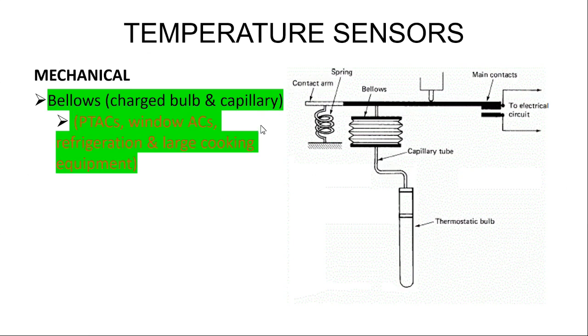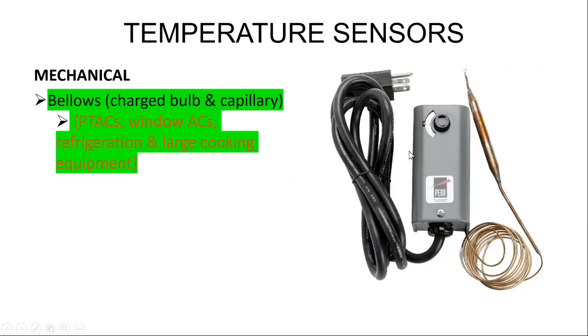You have the opposing spring tension, which opposes the action of the bellows. Here you have your adjustment stem. Where it is set determines how much the bellows must expand or contract in order to close these electrical contacts. Here's an example of one to be used in a walk-in cooler or freezer. And here's the bulb and the capillary, which is charged with a refrigerant or some type of gas that will cause the bellows to expand or contract as it's heated or cooled.